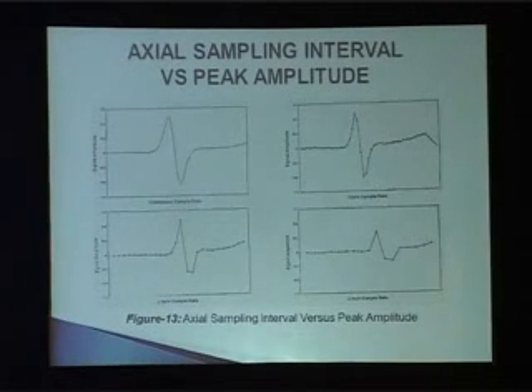This is axial sampling interval versus peak amplitude, with different sampling rates here. The first one is continuous sampling. The second one is a 0.1 inch sampling rate, then 0.2 inch, 0.3 inch. As you increase the distance, the peak becomes more and more blurred. Here the peak is big, and this signal can be recorded very nicely and analyzed.